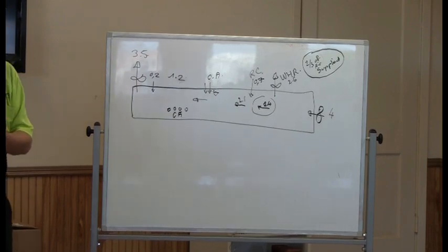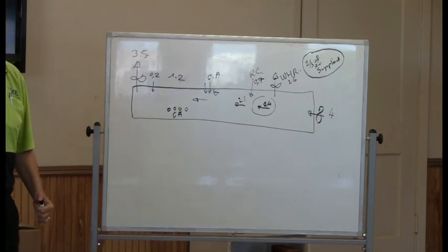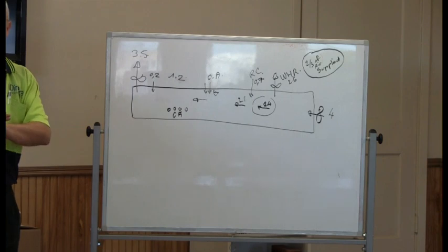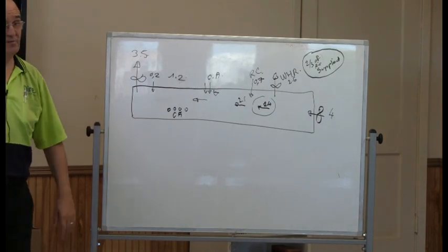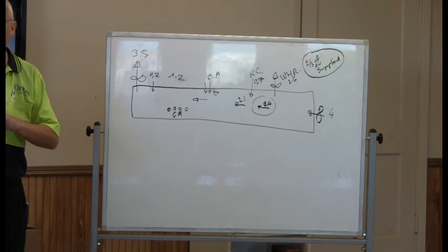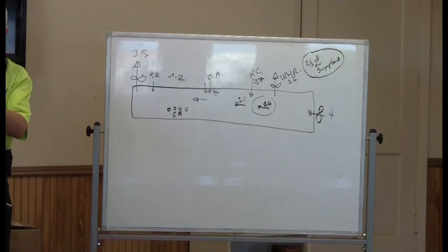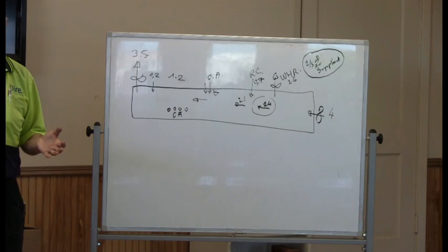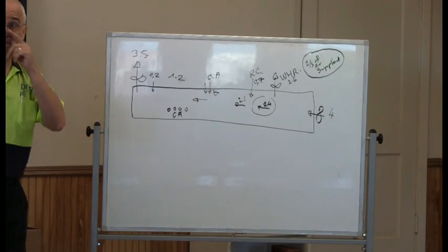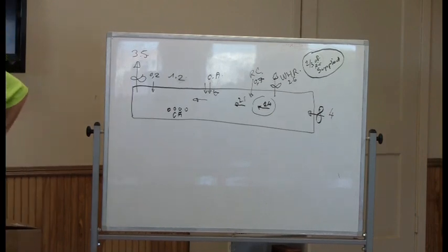As long as you can maintain it, fine. You reach a spot where you want to push more, so you're going to degrade this, you're going to degrade that. That happens everywhere. But if I established the ratio at 12 cars per day, and all the fans can maintain that ratio at 15 cars per day, it's purely mathematical, not in terms of speed of the fan, but in terms of mass delivery of the fan. Right. And the question is, at 12 cars a day your fans are giving you this, and you go to 16, and at some point there's a fan that cannot deliver what you calculate you need. And so that's the degrade you're talking about. Exactly. It can't quite make it.